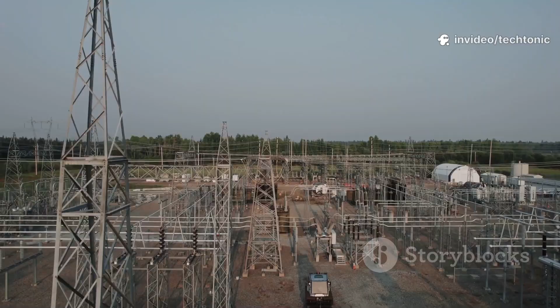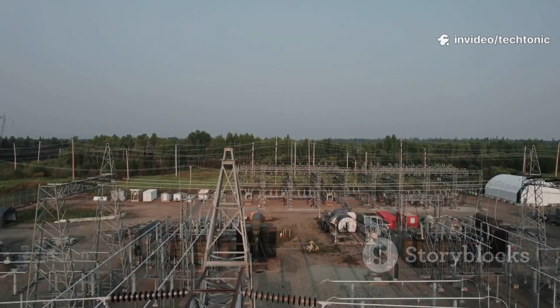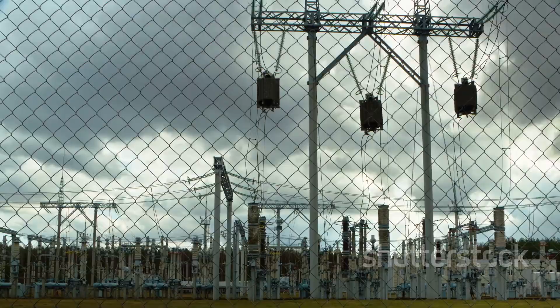Conductivity isn't the same everywhere. Moist, mineral-rich, and salty soils are the best for grounding electrical systems. That's why engineers often test soil before installing grounding equipment, searching for the best spots to ensure safety. At substations, you'll find huge grids of buried copper or other metals, all designed to make a strong, reliable connection to the Earth. These grids help safely disperse dangerous electrical currents. The main goal is to make it as easy as possible for fault currents, unexpected surges of electricity, to enter the ground and dissipate harmlessly.